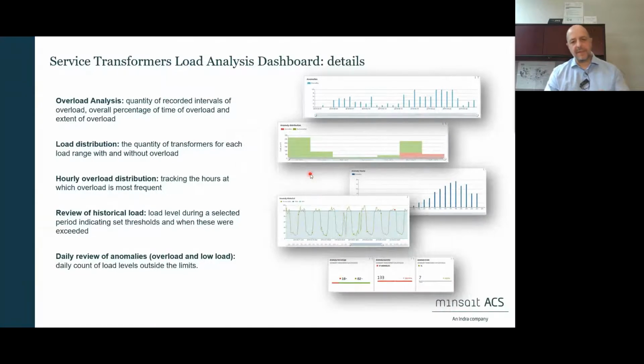In this case, we're aggregating to show the service transformer. So we're not taking the raw data from meters, analyzing meter by meter, but we are aggregating at service transformer level. Again, overload analysis, whenever the load of a transformer goes above 100% or above 90%, for example, of the nameplate. The load distribution during the day: when is the transformer mostly loaded during the 24 hours of the day, or maybe the day of the week. Hourly overload distribution during the 24 hours of the day.